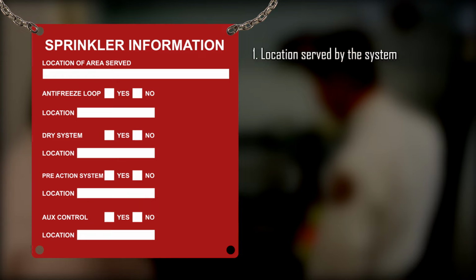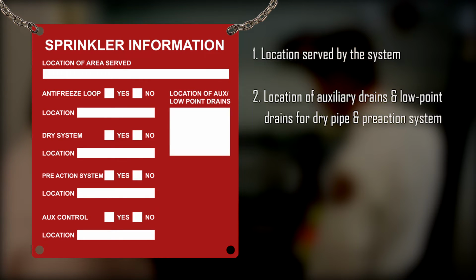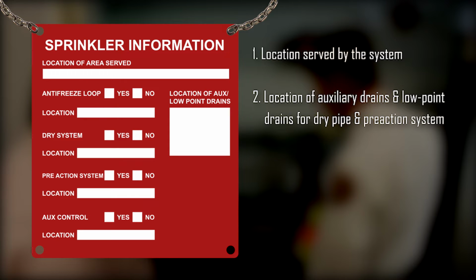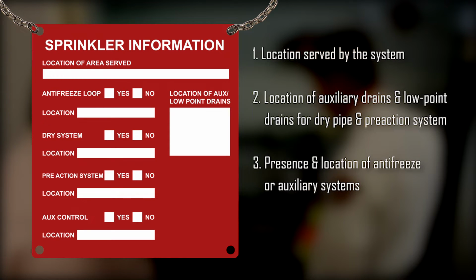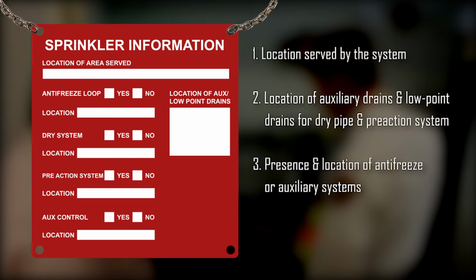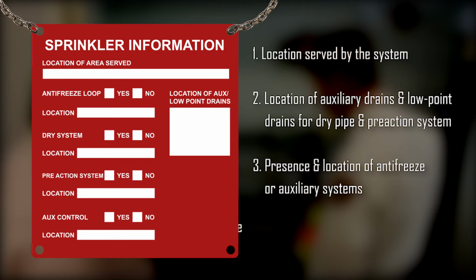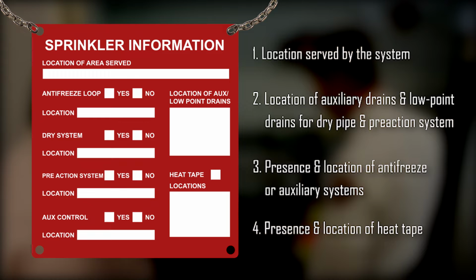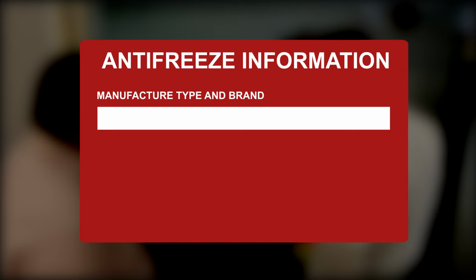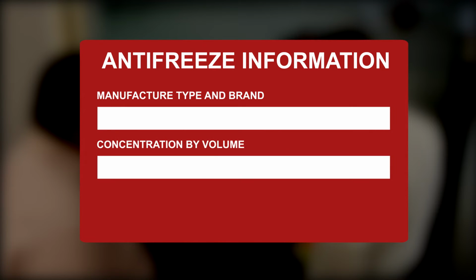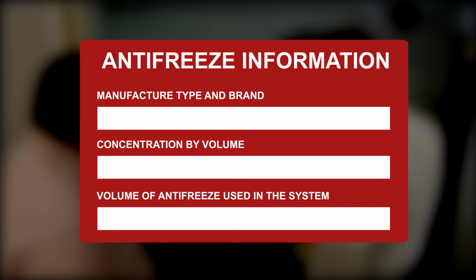1. The location of the area served by the system. 2. The location of auxiliary drains and low-point drains for dry pipe and pre-action systems. 3. The presence and location of antifreeze or other auxiliary systems. And 4. The presence and locations of heat tape. In addition, if antifreeze is used, place an antifreeze information sign on the antifreeze system main valve. The sign should indicate the manufacturer type and brand of the antifreeze solution used, the concentration by volume, and the volume of antifreeze used in the system.